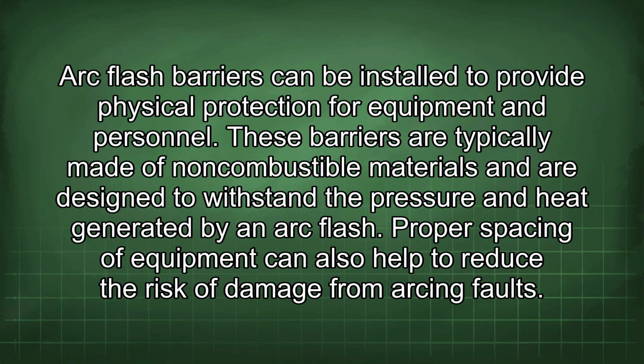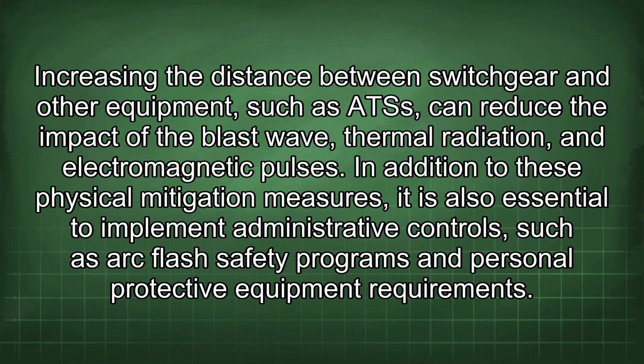Arc flash barriers can be installed to provide physical protection for equipment and personnel. These barriers are typically made of non-combustible materials and are designed to withstand the pressure and heat generated by an arc flash. Proper spacing of equipment can also help to reduce the risk of damage from arcing faults. Increasing the distance between switchgear and other equipment, such as ATS, can reduce the impact of the blast wave, thermal radiation, and electromagnetic pulses. In addition to these physical mitigation measures, it is also essential to implement administrative controls, such as arc flash safety programs and personal protective equipment requirements.